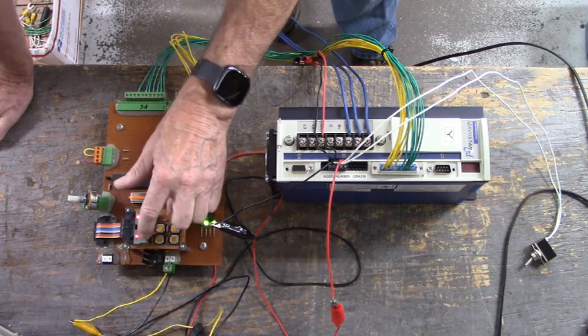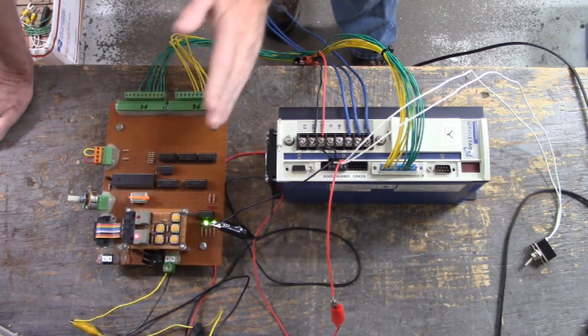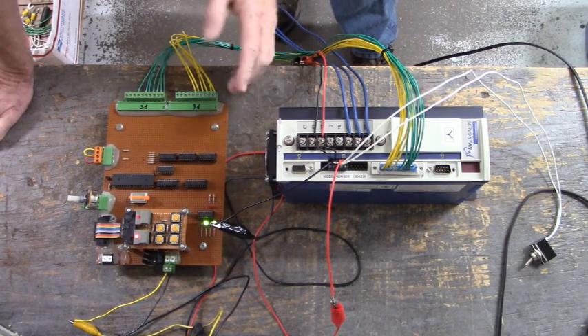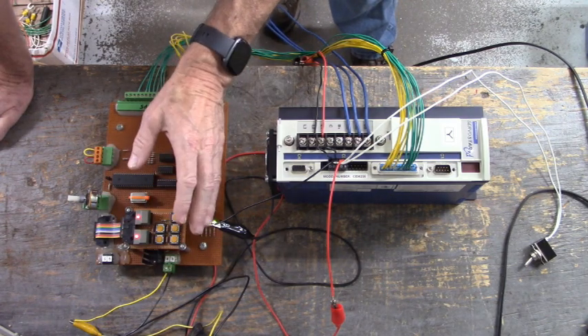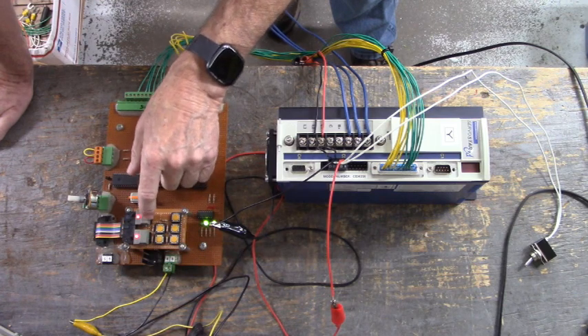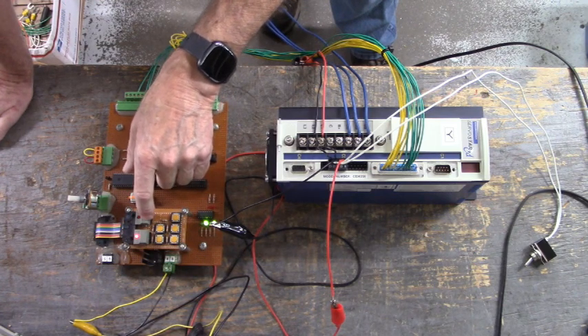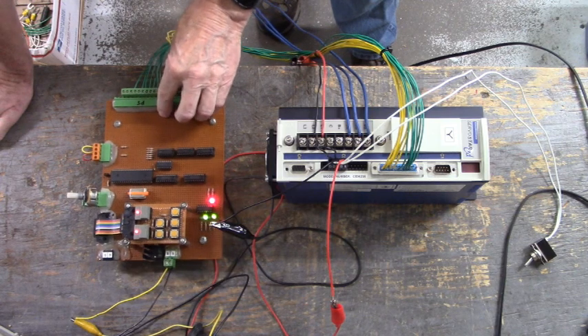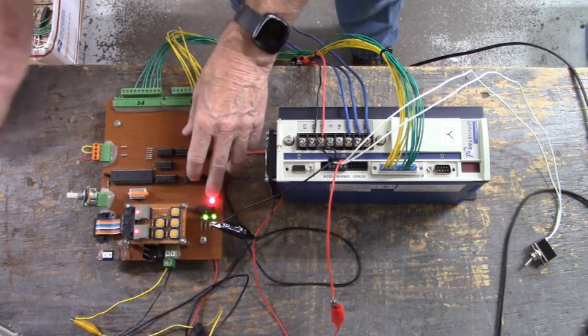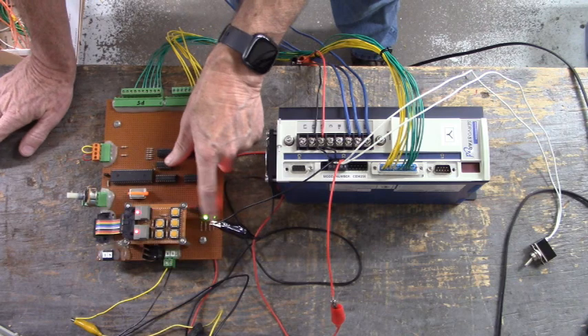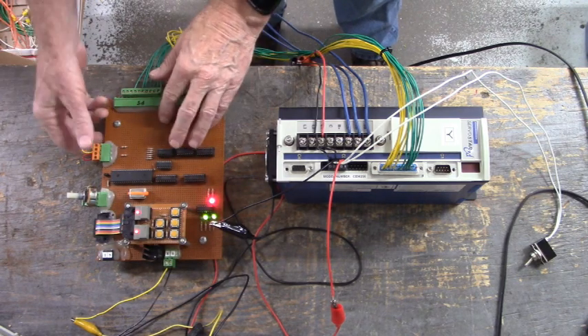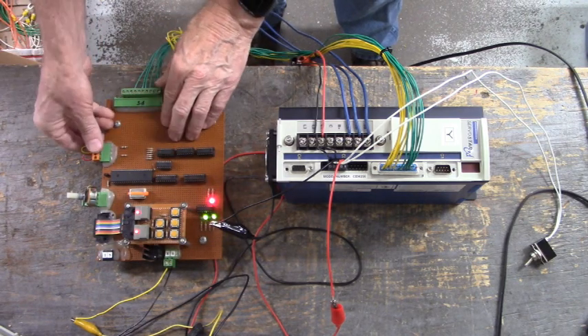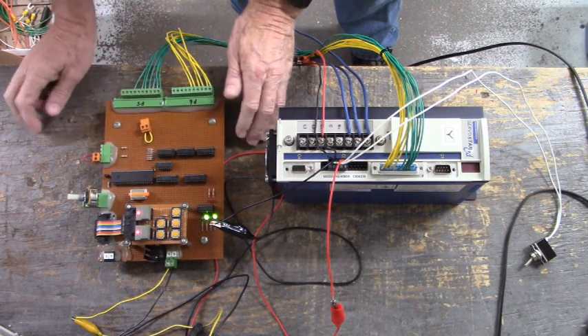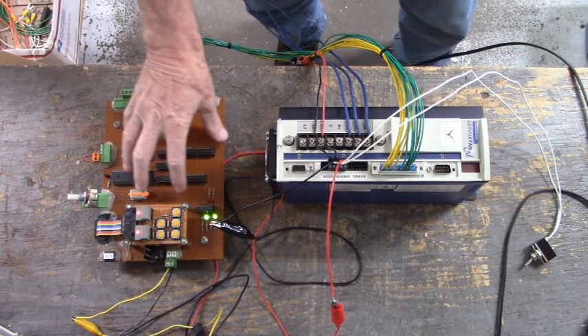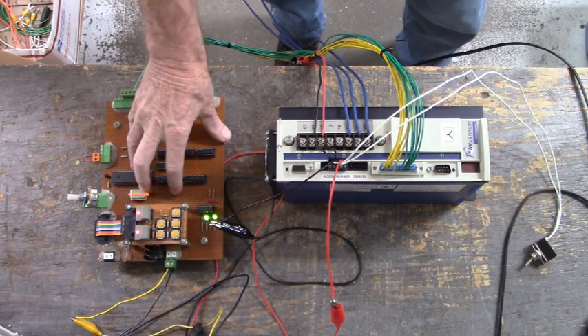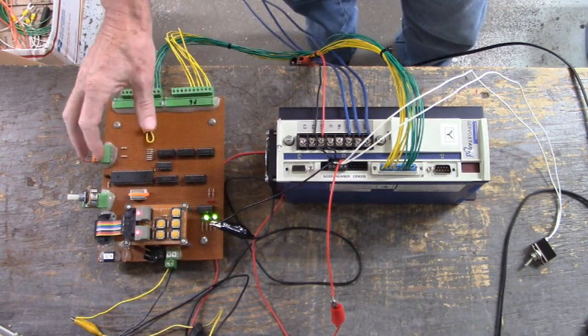Now we're going to select the home pulse on the leading edge of the B pulse, and then we're going to select a wide home pulse. Now we're running, indicated by this LED. These two LEDs right here indicate that we're differential output on the encoder side and the Hall Effect side. Let's disable that output real quick. So now the Hall Effect incremental encoder is not rotating.